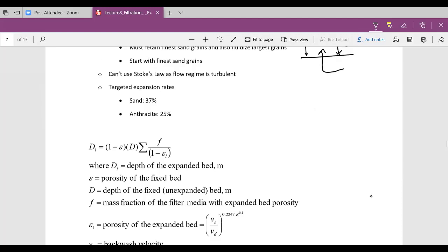Back many years ago at the East Lansing Meridian Township plant, when they first put in anthracite within their sand filters, they didn't calculate the backwash rates properly and actually washed out much of their anthracite. They ended up having to rebuild their filters, which was costly, and also had to reduce their backwash rate.